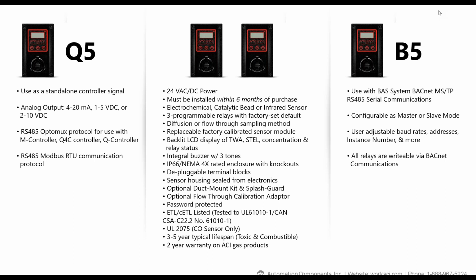The B5 is the BACnet sensor, BACnet MSTP. Pretty much what it is, it has all the same features: 3 relays, horn buzzer, LCD, NEMA 4X enclosure. You can also change the baud rates on the front using the keypad on the sensor—if you need to go from 9600 up to, I think, 115,200 or so. All the relays are writable via BACnet.